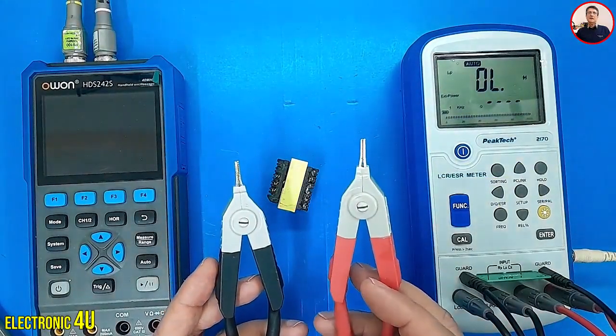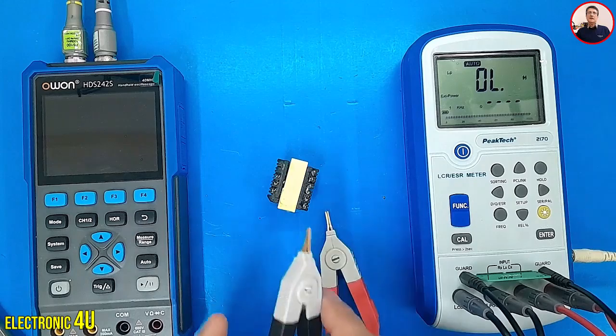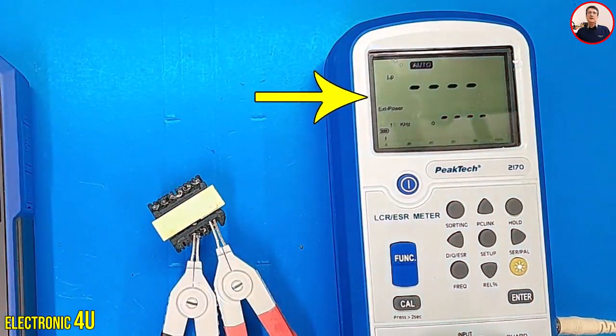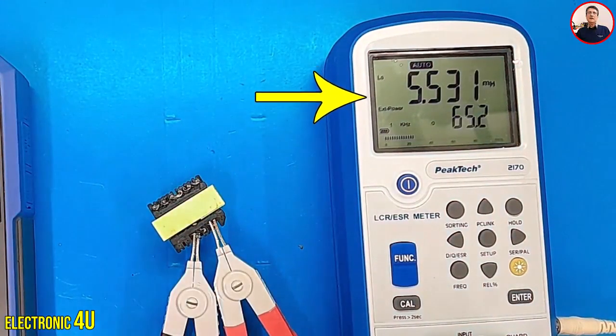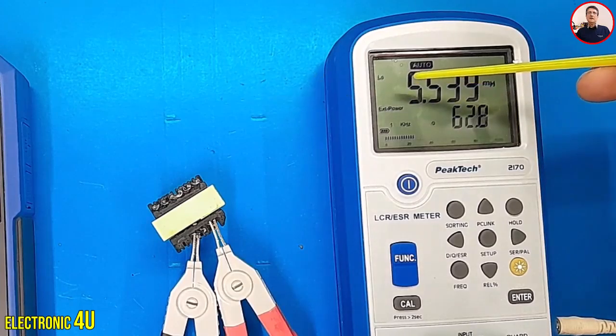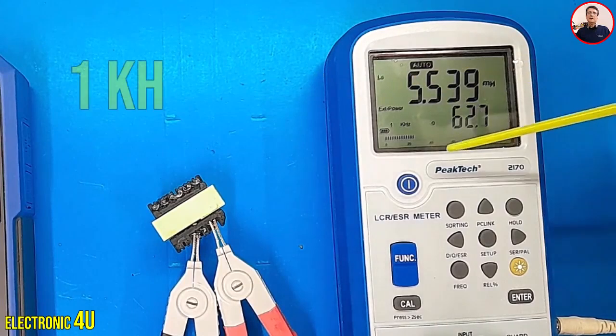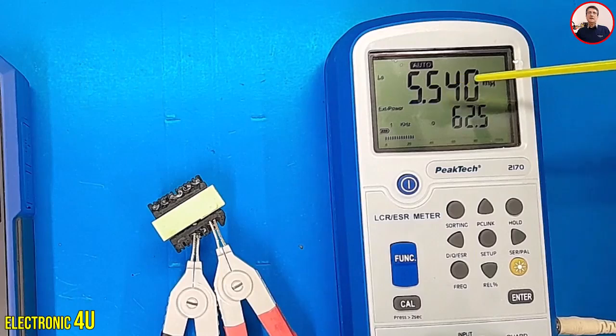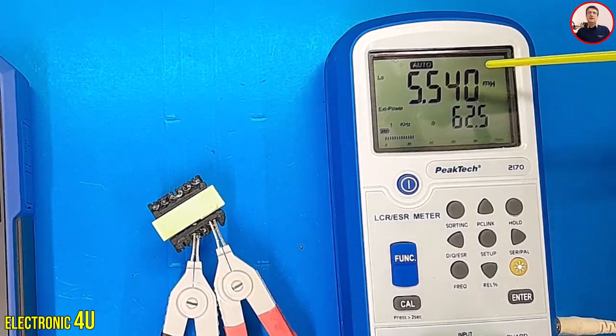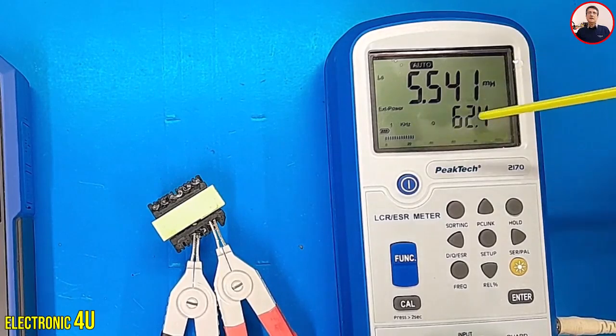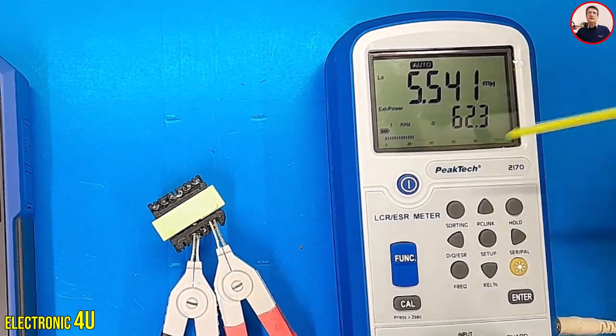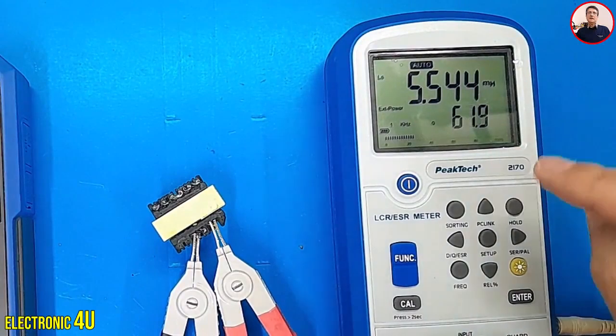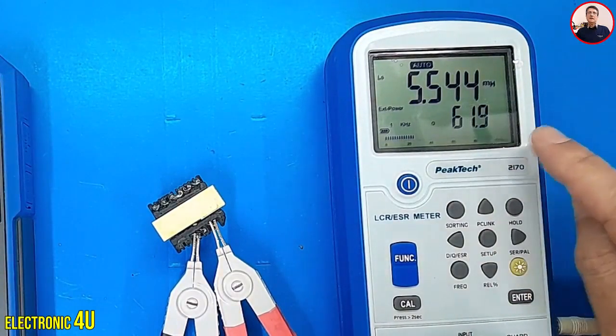I connect the clips to the transformer's primary winding. The LCR meter displays the series parameters for this inductor. The frequency is set to 1 kHz. The inductance is 5.540 mH. Since we don't know the exact inductance value, what is important to us? The secondary parameters are displayed below. By pressing this button, we can view the secondary parameters.